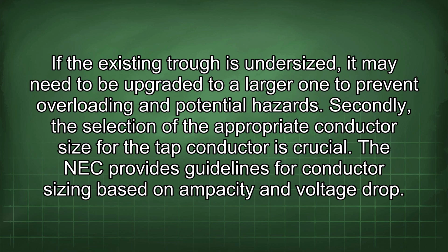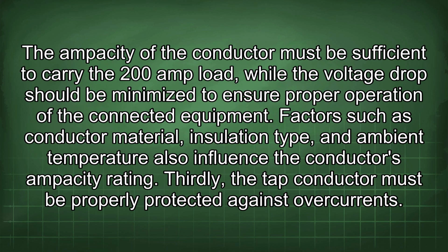If the existing trough is undersized, it may need to be upgraded to a larger one to prevent overloading and potential hazards. Secondly, the selection of the appropriate conductor size for the tap conductor is crucial. The NEC provides guidelines for conductor sizing based on ampacity and voltage drop. The ampacity of the conductor must be sufficient to carry the 200 amp load, while the voltage drop should be minimized to ensure proper operation of the connected equipment.